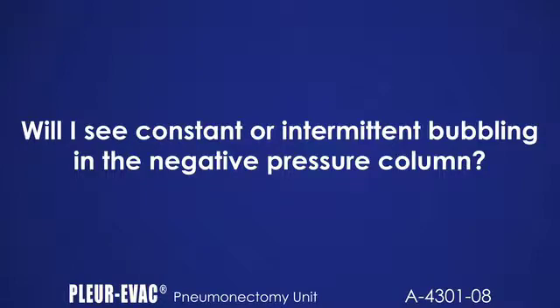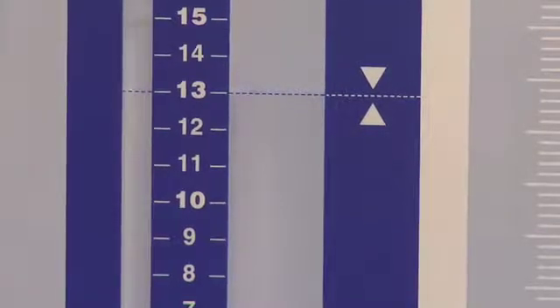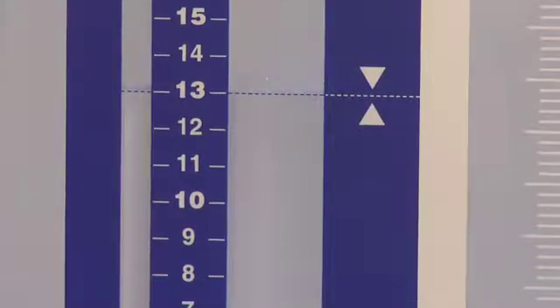Will I see constant or intermittent bubbling in the negative pressure column? You will see bubbling in the negative pressure column if the patient attains negative pressure equal to the height of the fluid, i.e., 13 centimeters. This may occur with or without the presence of a volume ventilator system or other external factor. If you do not see any bubbling in the blue negative pressure column, that indicates the patient pressure is above minus 13 centimeters of water, which is common. You may see some fluctuation in the column with respiration.